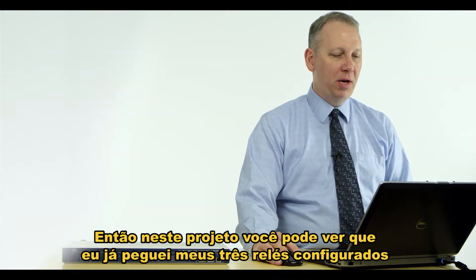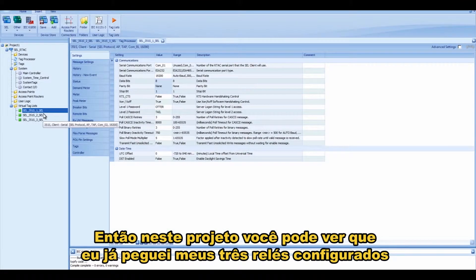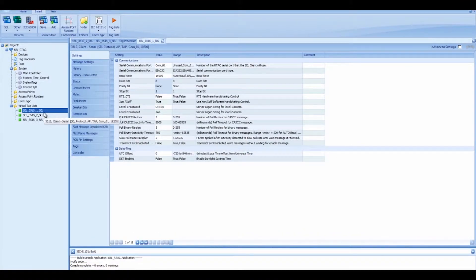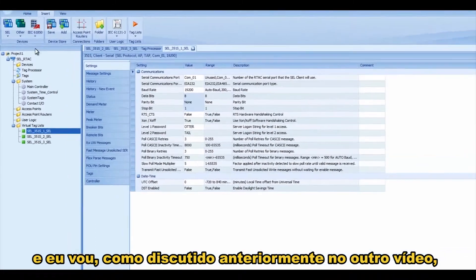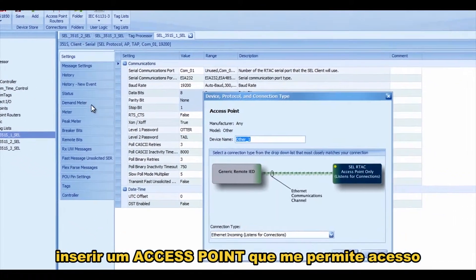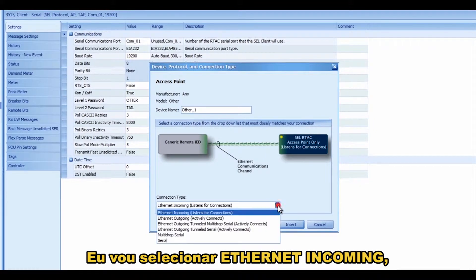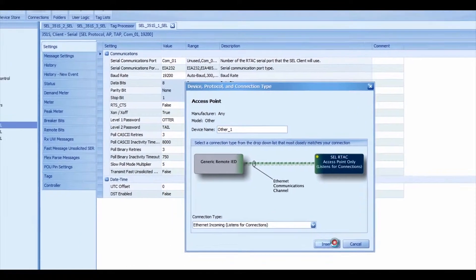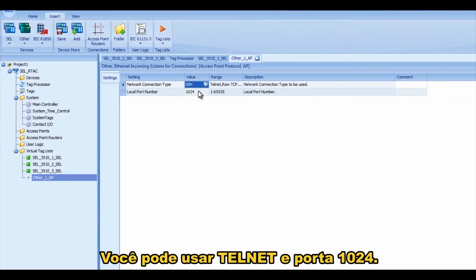In this project I've already got my three SEL relays configured, and as discussed earlier in the other video, I'm going to insert an access point to allow remote access. I'll select Ethernet incoming, press Enter, and make it an SSH connection — you can also use Telnet — on port 1024.